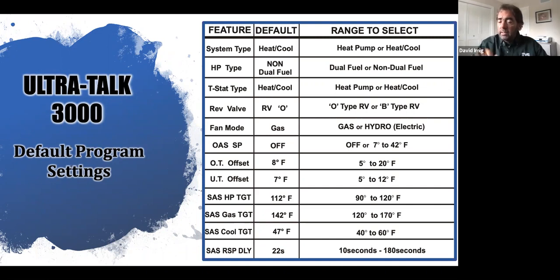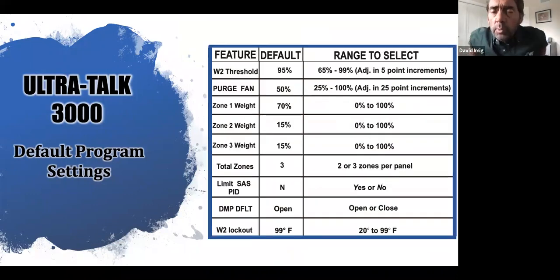My response delay is how often my supply air sensor is looking at the target temperature and feeding that information back to the UT-3000. I'll go through that operation where that makes a little more sense. But again, I'm going to look every 22 seconds and I'm looking to achieve 112, 142, or 47. If I haven't, my system demand goes up, and system demand is part of the operation that allows me to stage up or stage down the equipment. I'll show you that here in a bit when we get to the rest of the settings.